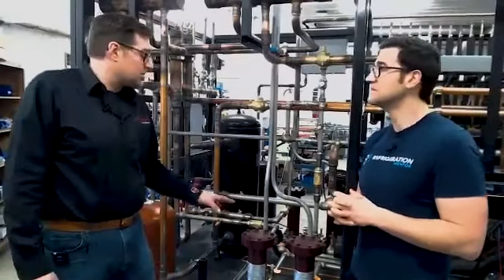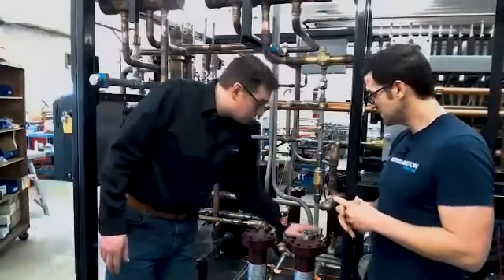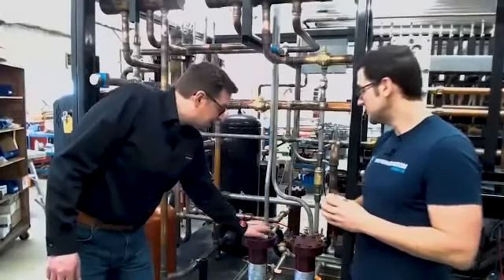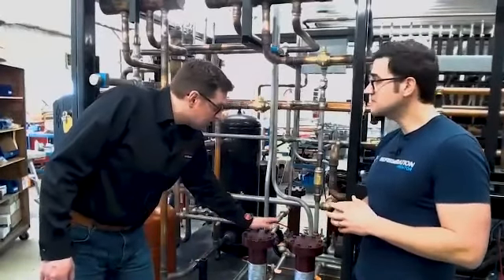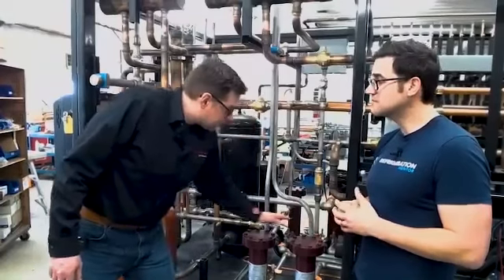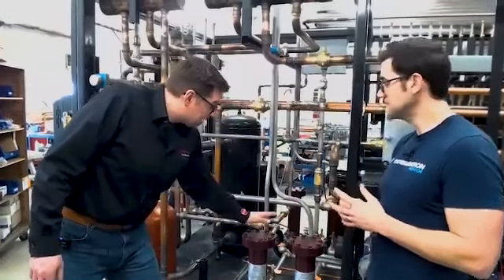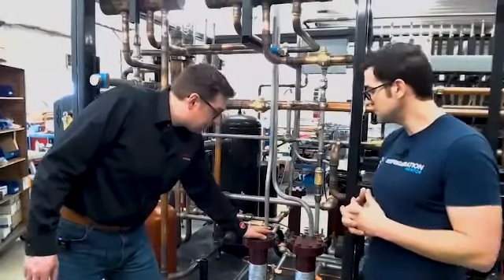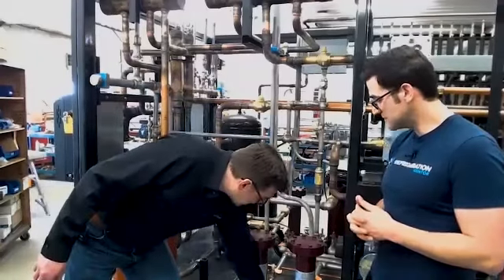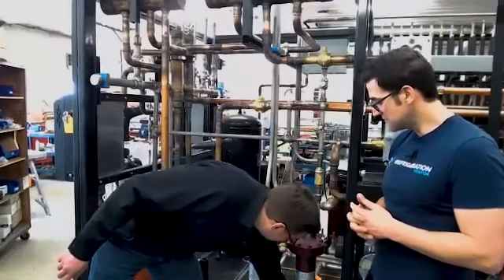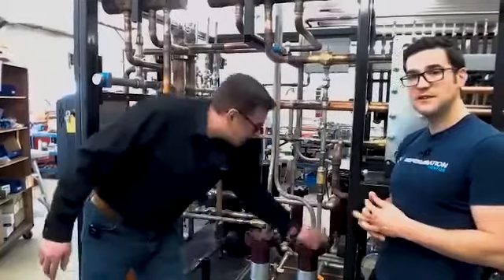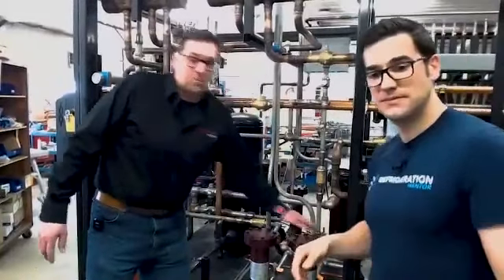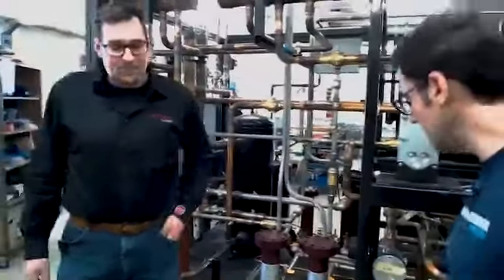And even in a basic supermarket application, our principle is always to have independent groups. So you can isolate 50% of the rack and leave the other 50% running. So if I'm coming to do my service, I can isolate this temp right, change my oil filter, do my oil test, change my Swagelok oil filter here in the back, but yet my 50% of my other rack is still moving. Yeah, we're just going to move this up so we can take a better look at that.